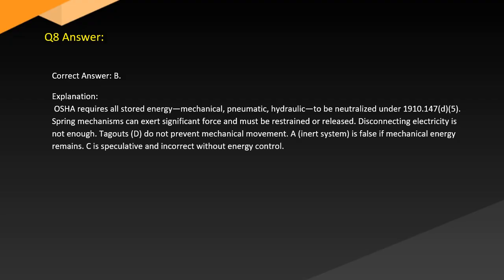Answer. Correct answer: B. Explanation. OSHA requires all stored energy, mechanical, pneumatic, hydraulic, to be neutralized under 1910.147(d)(5). Spring mechanisms can exert significant force and must be restrained or released. Disconnecting electricity is not enough. D, tagouts do not prevent mechanical movement. A, the system is inert, is false if mechanical energy remains. C is speculative and incorrect without energy control.